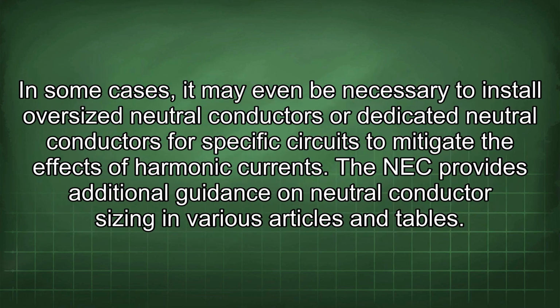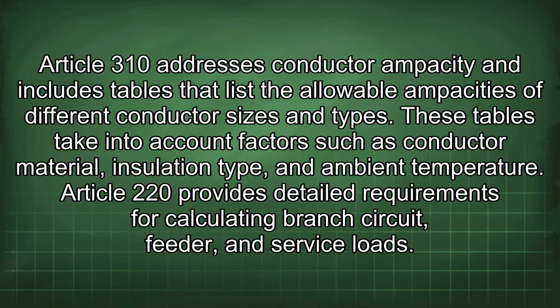In some cases, it may even be necessary to install oversized neutral conductors or dedicated neutral conductors for specific circuits to mitigate the effects of harmonic currents. The NEC provides additional guidance on neutral conductor sizing in various articles and tables. Article 310 addresses conductor ampacity and includes tables that list the allowable ampacities of different conductor sizes and types. These tables take into account factors such as conductor material, insulation type, and ambient temperature.